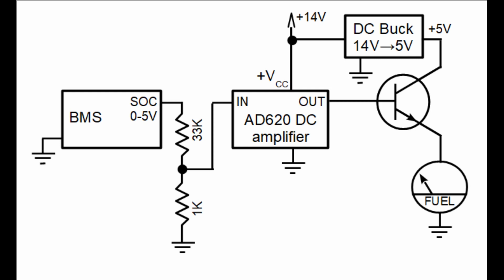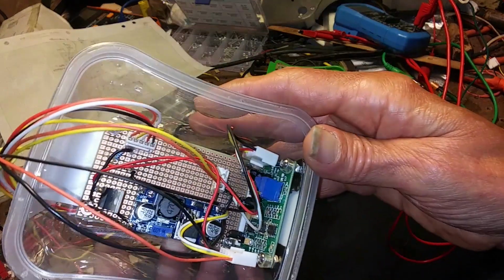Of course, the gauge reading will change a little bit as the ambient temperature changes from, say, 0 to 30 degrees centigrade. But the maximum change is only plus or minus 40 millivolts, so about a 2% error in the gauge reading, and I think that's tolerable.